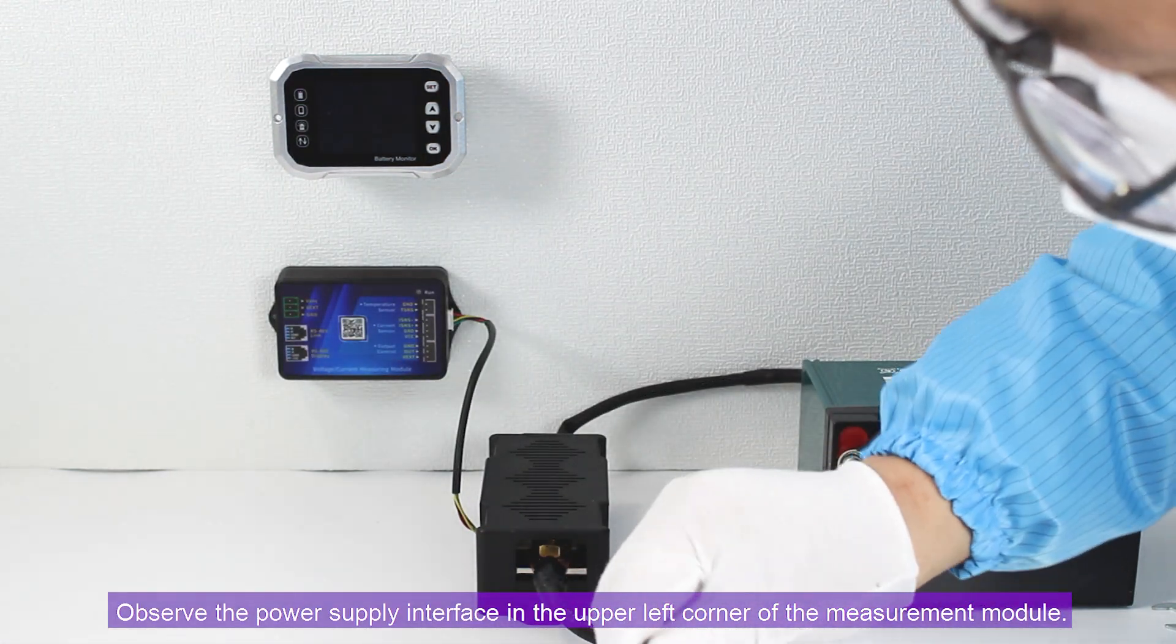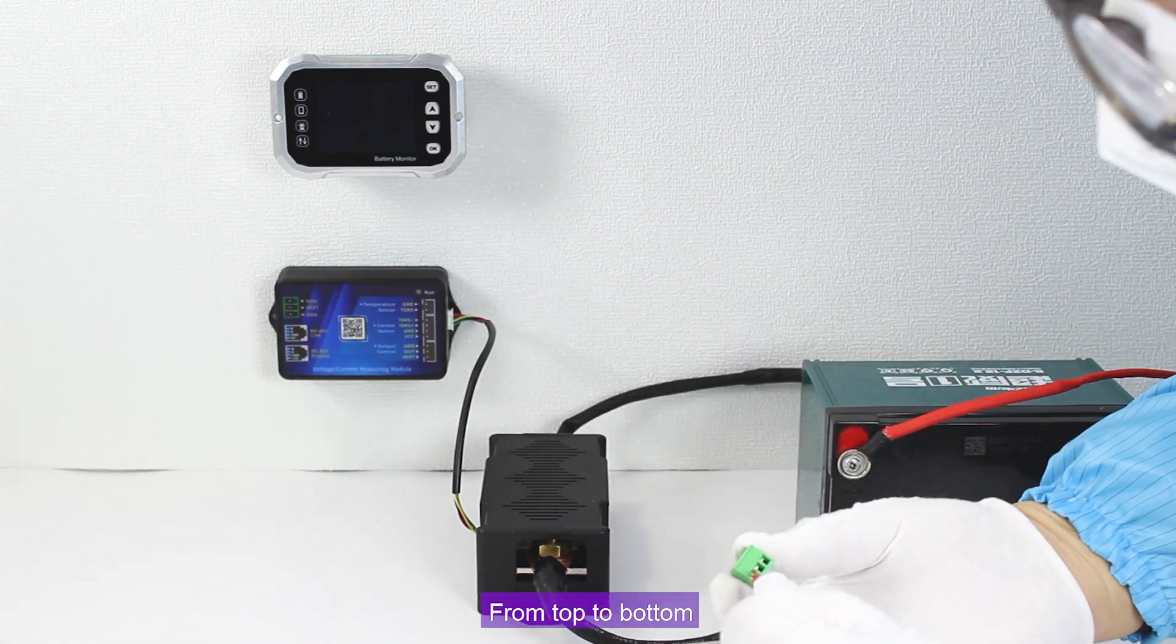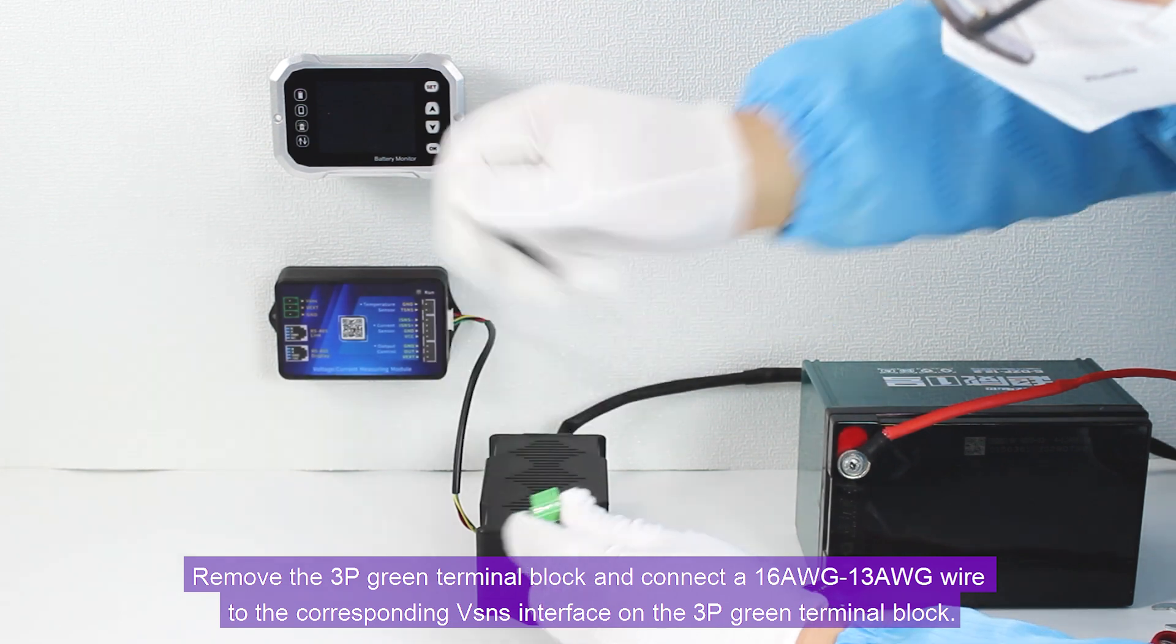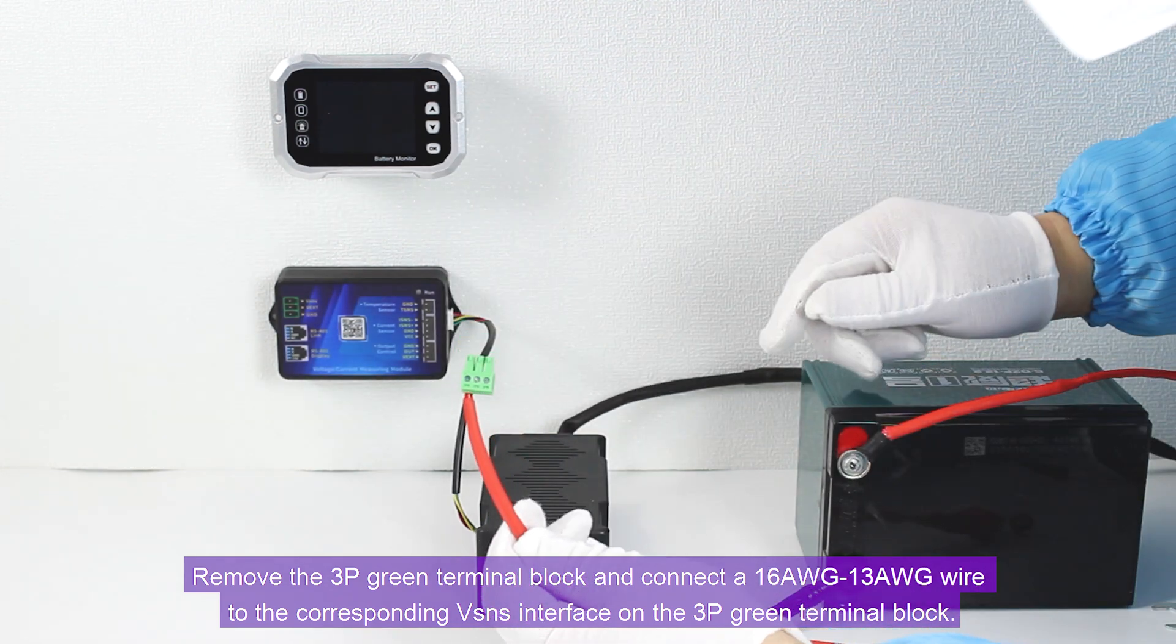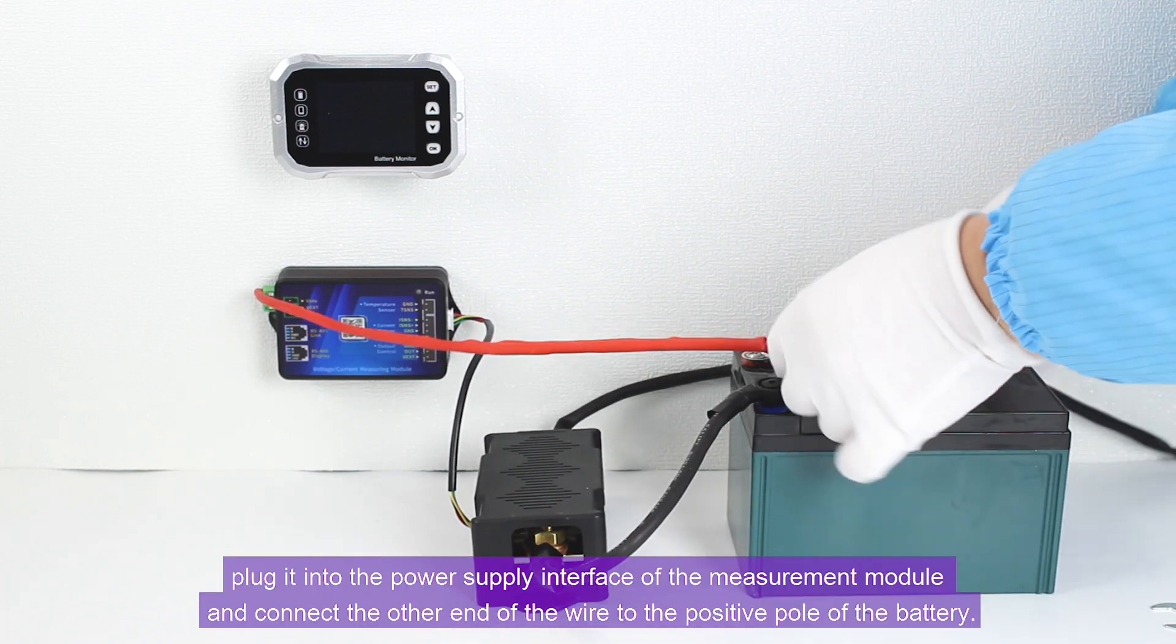Observe the power supply interface in the upper left corner of the measurement module. From top to bottom they are VSNS, VEXT, and GND. Remove the 3P green terminal block and connect a 16 AWG to 13 AWG wire to the corresponding VSNS interface on the 3P green terminal block. After connecting it, plug it into the power supply interface of the measurement module.